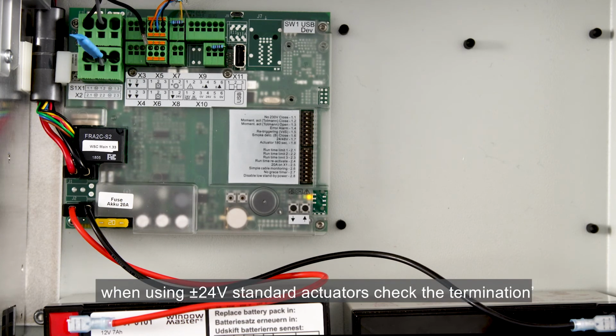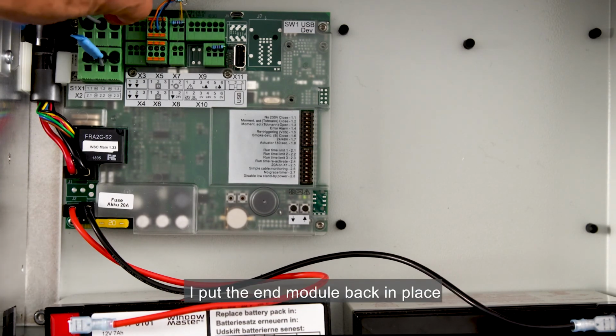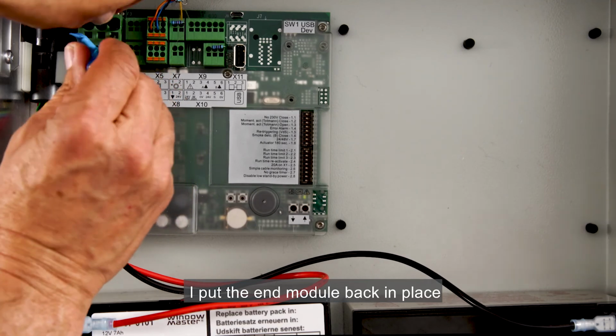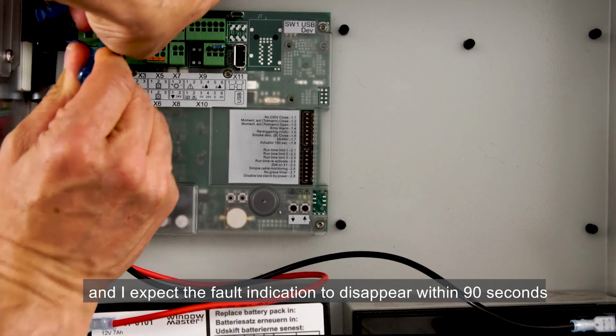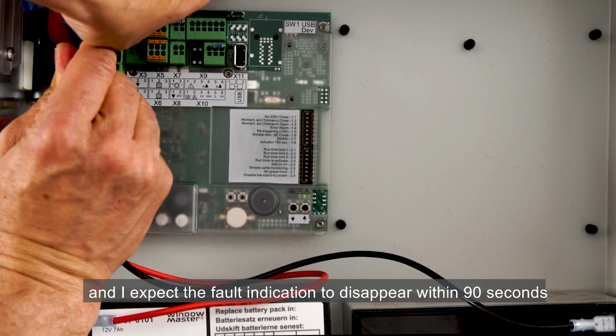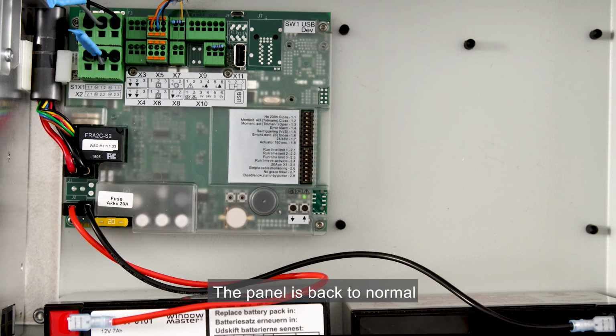When using plus/minus 24 volt standard actuators, check the termination. I put the end module back in place and I expect the fault indication to disappear within 90 seconds. The panel is back to normal.